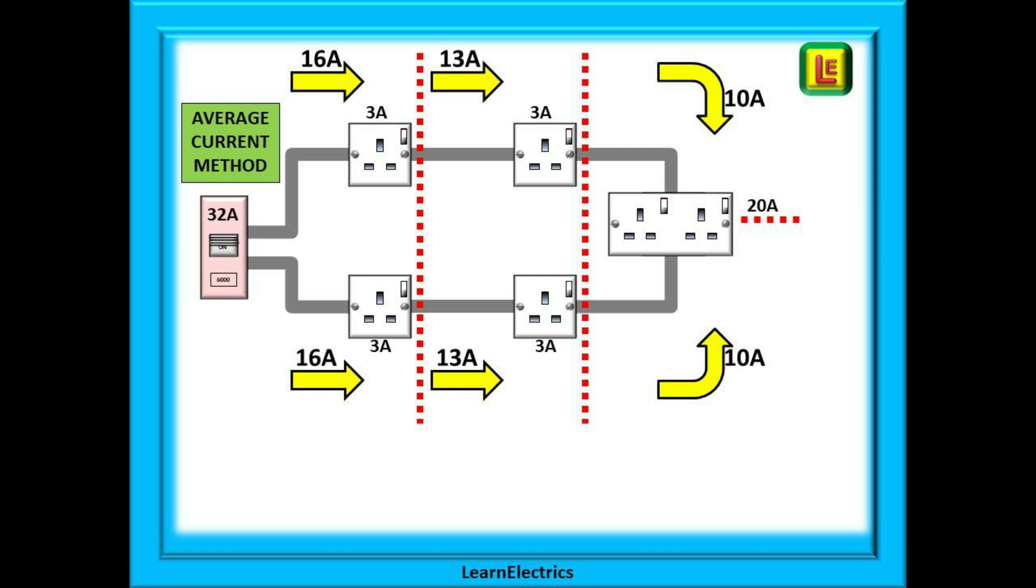If we look at this on the circuit drawing we can see that the first section of the upper leg from the breaker will carry 16 amps of current, and so will the first section of the lower leg, another 16 amps. At the first socket on each leg, 3 amps will be tapped off. This leaves 13 amps for the second section where another 3 amps is used.